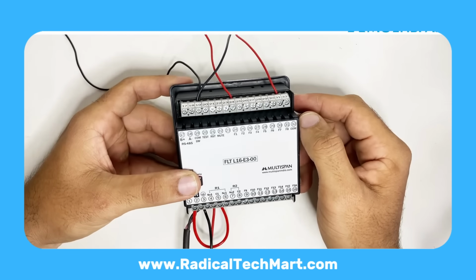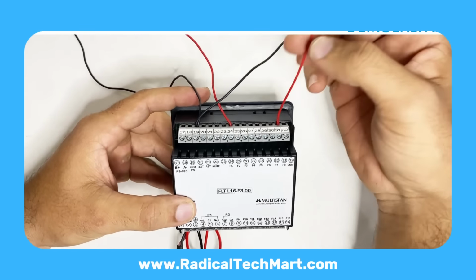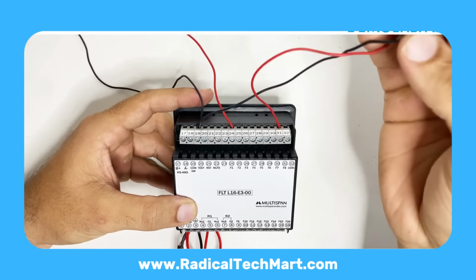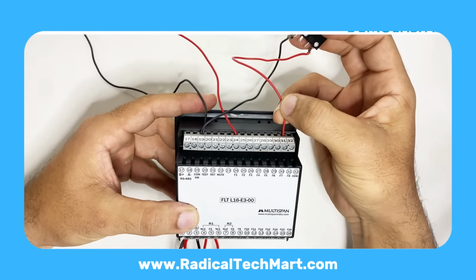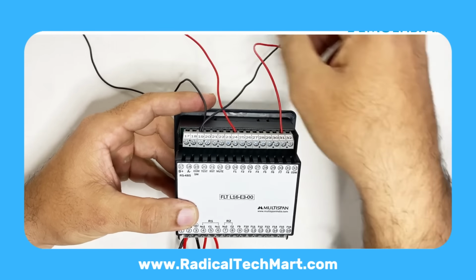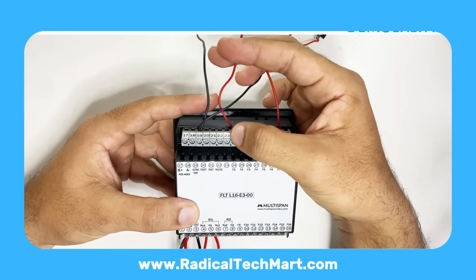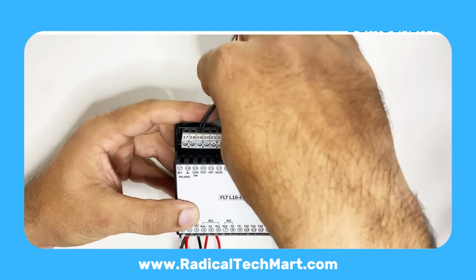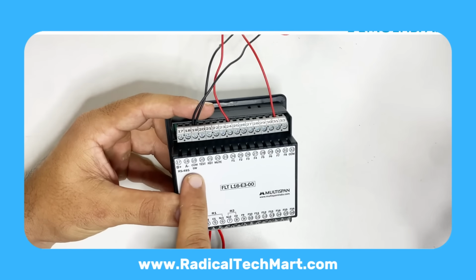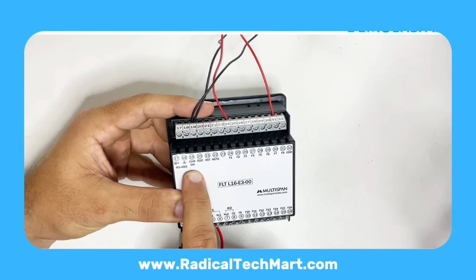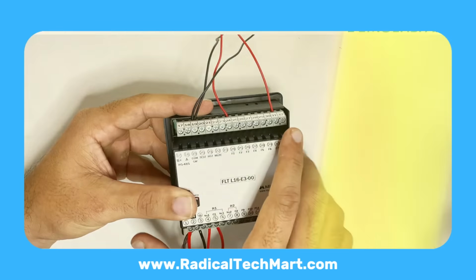To generate faults for demo, we've used two switches, one wired to F8 and one to F1. The common terminal for these fault switches is terminal 19, which is the input common for fault contacts. So whenever we operate these switches, we simulate a fault on those specific channels.